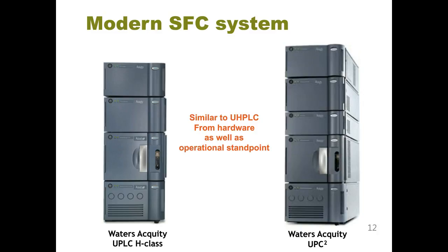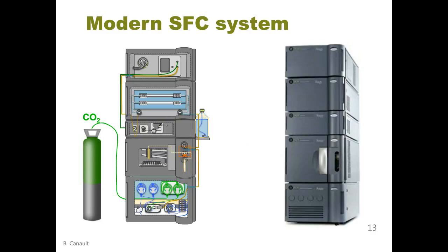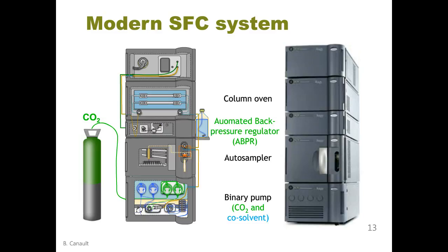From an operational standpoint, modern SFC systems are very similar to modern LC systems. Inside, you will find the usual LC elements: a binary pump, an auto-sampler, a column oven, and a diode array detector. The particular SFC features include the CO2 pump being cooled to a low temperature so CO2 is pumped as a liquid for efficient flow rate control, and an automated back pressure regulator to control the state of the fluid and maintain a homogeneous mixture between CO2 and co-solvent.